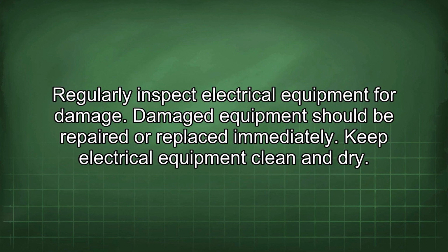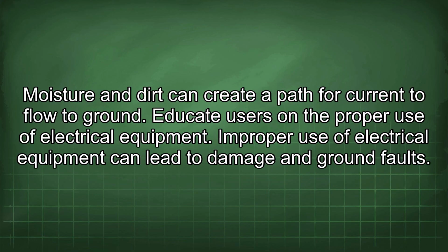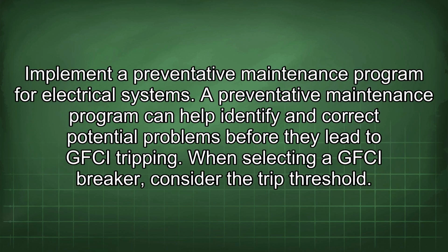Regularly inspect electrical equipment for damage. Damaged equipment should be repaired or replaced immediately. Keep electrical equipment clean and dry. Moisture and dirt can create a path for current to flow to ground. Educate users on the proper use of electrical equipment. Improper use of electrical equipment can lead to damage and ground faults. Implement a preventative maintenance program for electrical systems. A preventative maintenance program can help identify and correct potential problems before they lead to GFCI tripping.